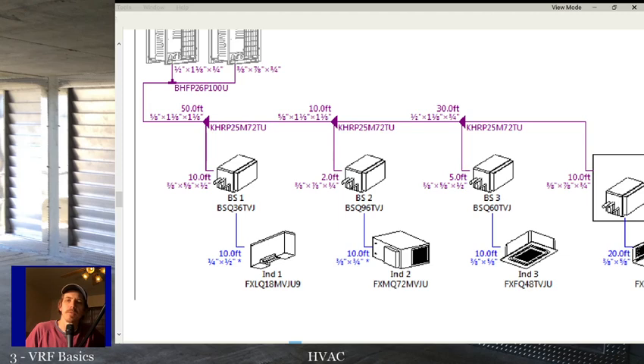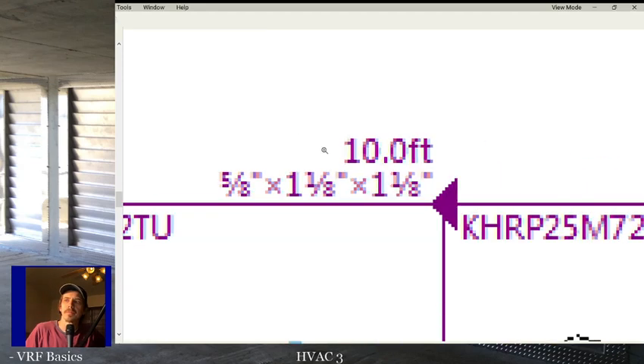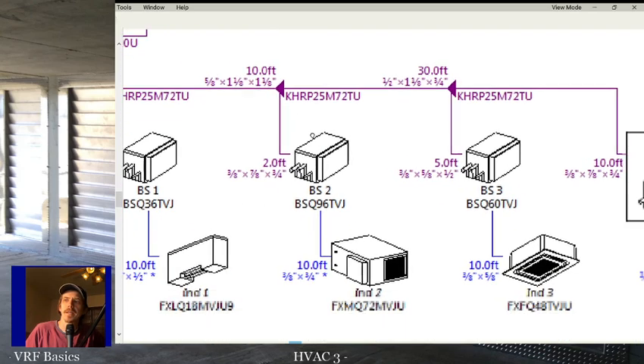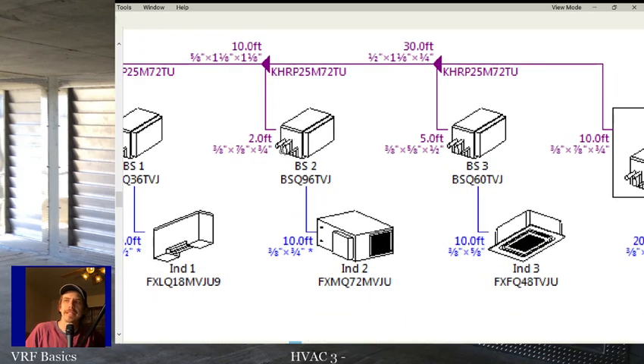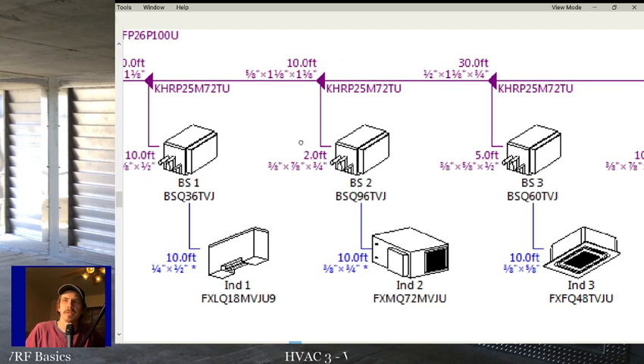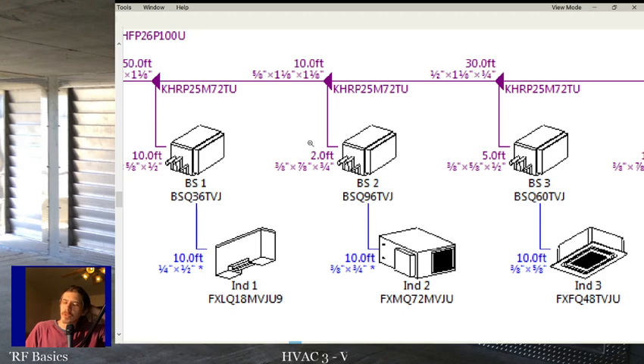The other thing that comes up a lot with these is minimum distance between components. So if you look at this diagram, it shows 2 feet from this Y to this branch selector. That's pushing it. 2 feet is like your minimum between components because you need room for that refrigerant to lose its turbulence, basically achieve laminar flow again as it hits a component, because there's going to be turbulence in that piping.